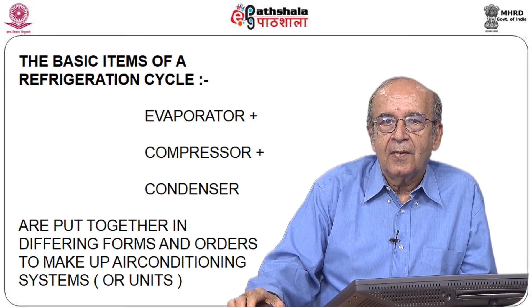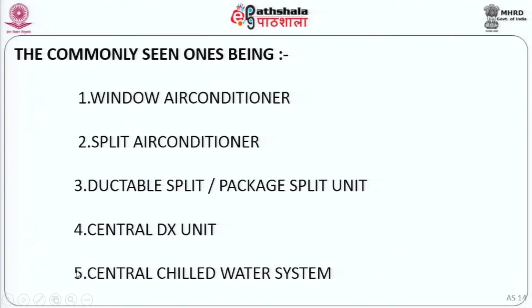The next one is a split air conditioner, which is basically, as the word says, a split of the two. Next, you have a ductable split, which is a larger version of this, and you also have the larger version of the three devices put together, which is called a central DX unit. This particular unit has a handicap that it is a single zone device, and when it is to be used for multi-zone applications, this gives way to a central chilled water system.